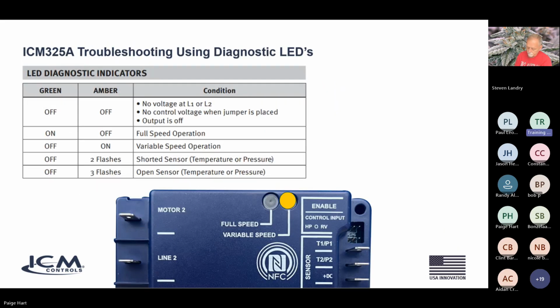So once you get everything wired up, she starts up. If everything goes well, the control will sense what the pressure is and or the temperature, and it might wait a few seconds for the pressure to build up to a certain range where it needs to turn on the fan. Because remember, when the control senses it doesn't need the fan, it'll keep that fan off. When it does need the fan, it'll turn it on either at full speed if it needs it, or at variable speed if it should be in variable. So you turn on the unit, maybe it takes a couple of seconds to build pressure, then the fan will come on at full speed for a very short hard start session, maybe a second or two, depending on how you have your hard start setting.